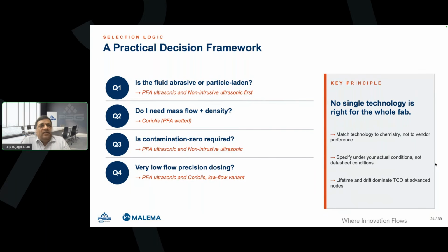Is a contamination-free product required, in which case either an inline PFA or a non-intrusive PFA like clamp-on can be applied. For low flow precision dosing in a coater application, photoresist dispense or spin-on dielectric type applications, PFA ultrasonic flow meters that can measure flow accurately at 1/8 inch line sizes and microliter volume dispenses could be a choice. So no single technology is right for the whole fab. There is a variety of technologies available, so we need to match the technology to the chemistry as well as to the application, not to the vendor preference, as I mentioned here.